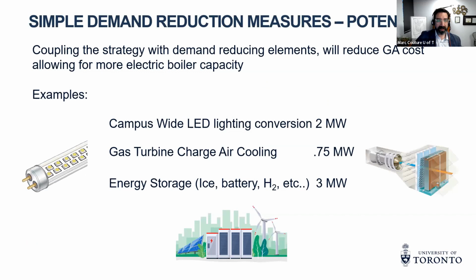We are looking at some demand reduction measures and their potential on our campus to help mitigate those peaks. Coupling the strategy with demand-reducing elements will reduce global adjustment costs, allowing for more electric boiler capacity. For example, we have a gas turbine on campus, and we can increase its output with some chiller cooling, which might give us close to a megawatt in extra demand reduction capability.